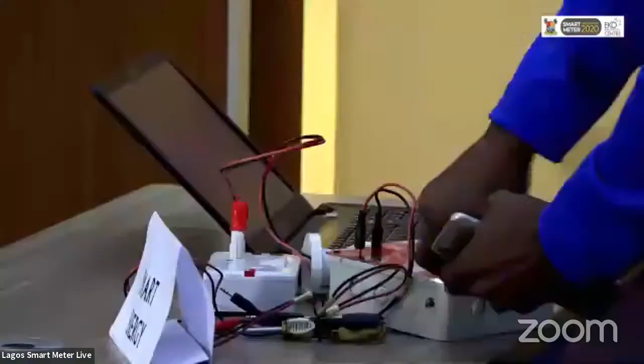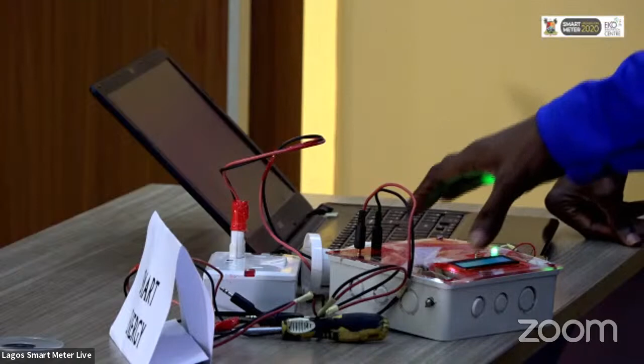Now for tampering, once someone tampers with the meter, maybe by opening the screw, it automatically trips off. When it trips off, the meter still stays open because it has an internal battery. That battery is just to keep it working so it can send data to the remote side indicating that this meter has been tampered with.